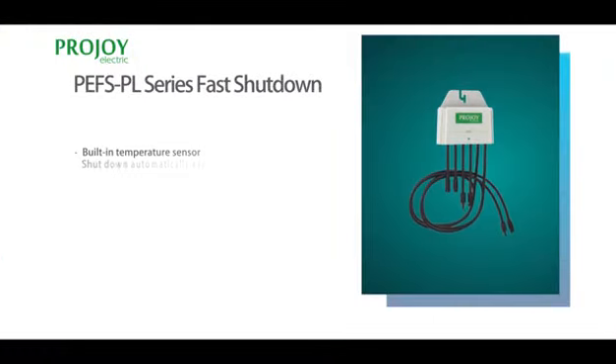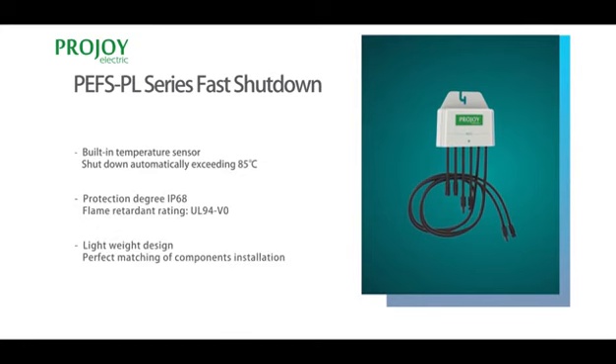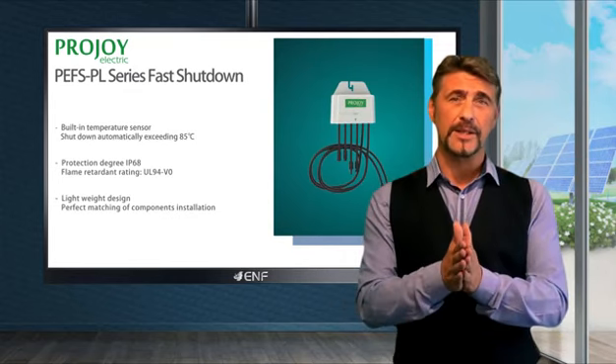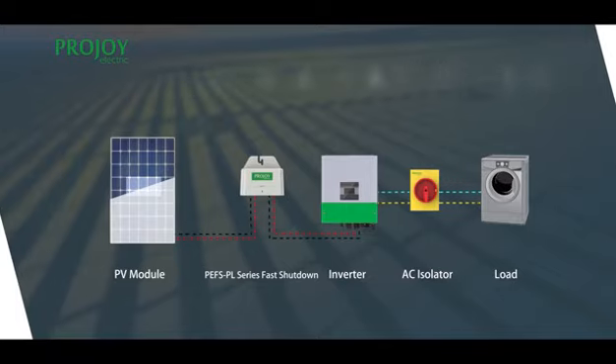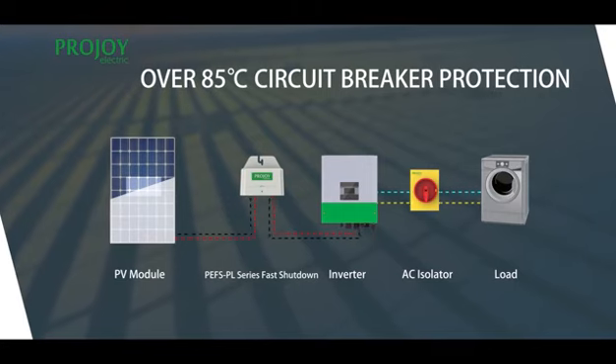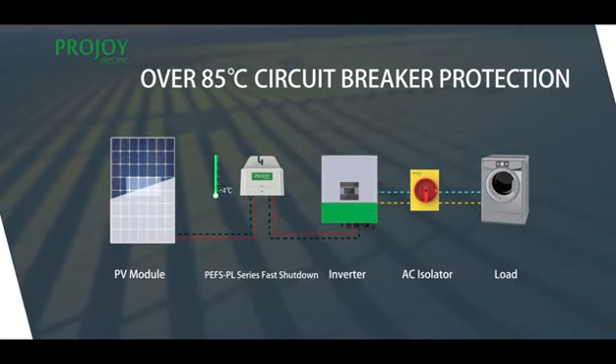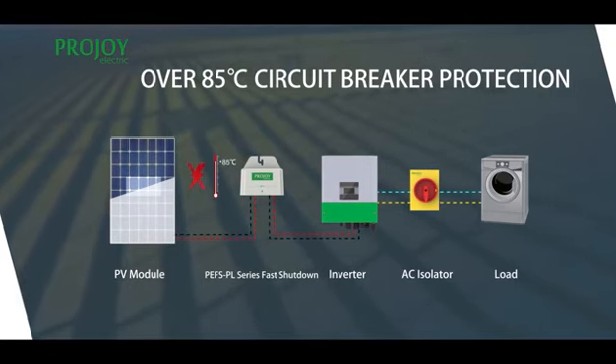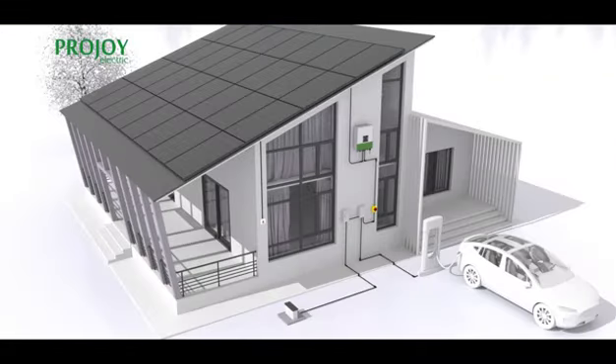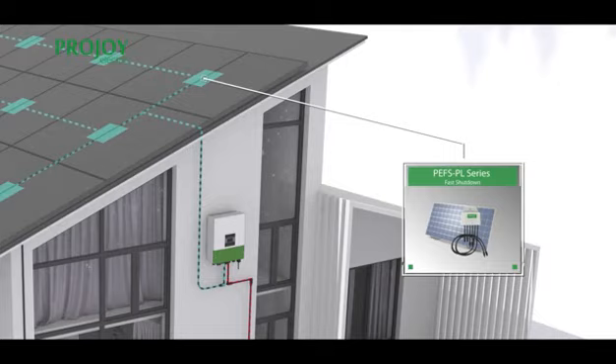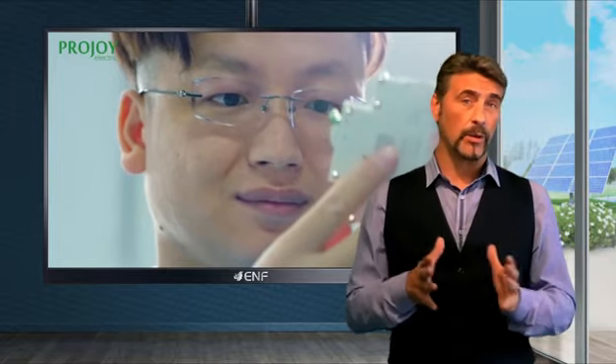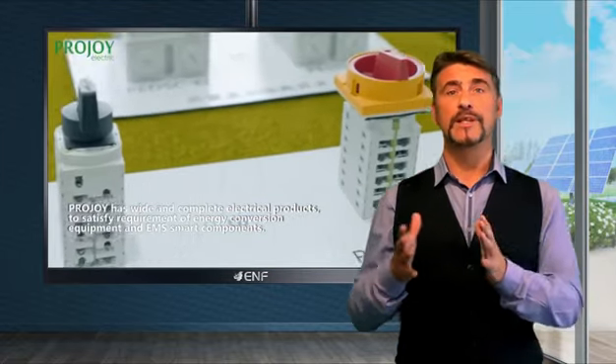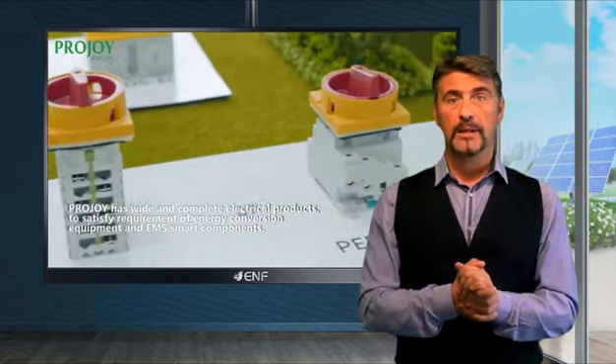Relying on an advanced temperature sensor that monitors the temperature inside the enclosure in real time, our fire safety switches have a built-in sensor that automatically shuts down the system when the temperature crosses 85 degrees Celsius, as in the case of fires. This reduces the DC voltage between each module to a safer level, thereby creating a safer situation for the firefighters.